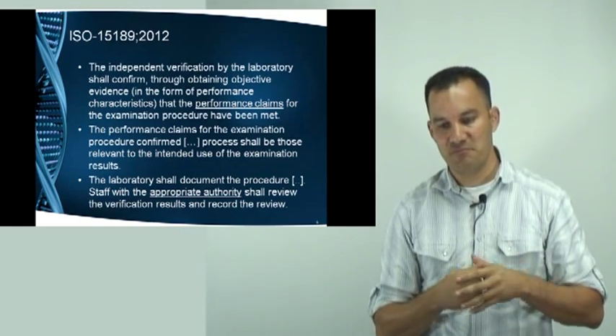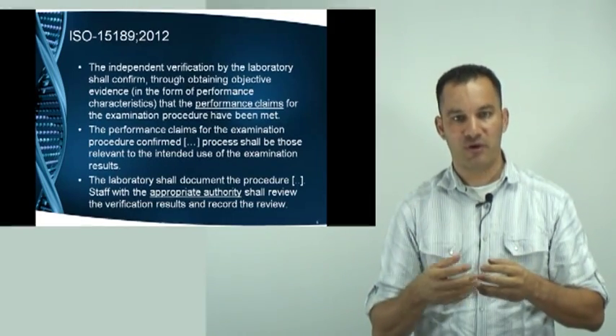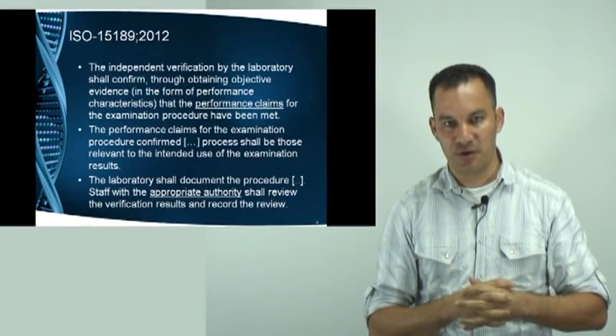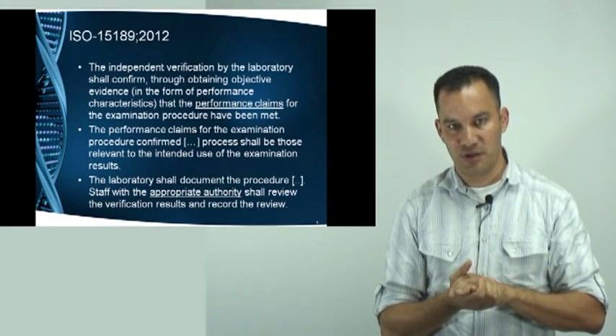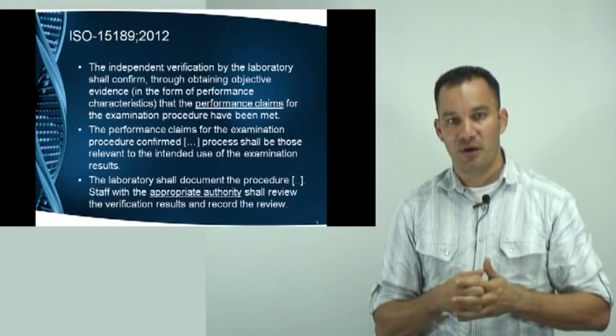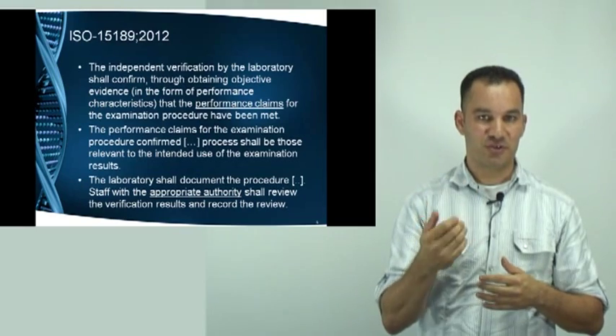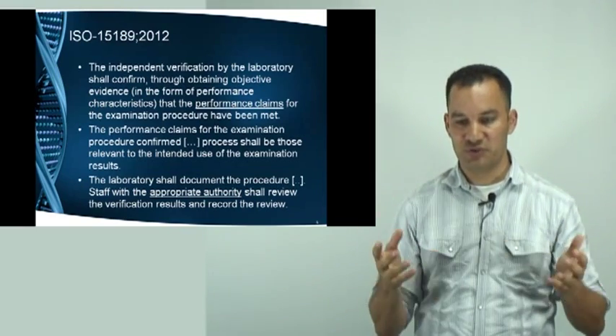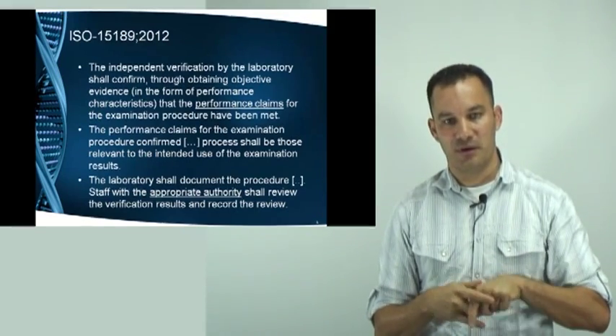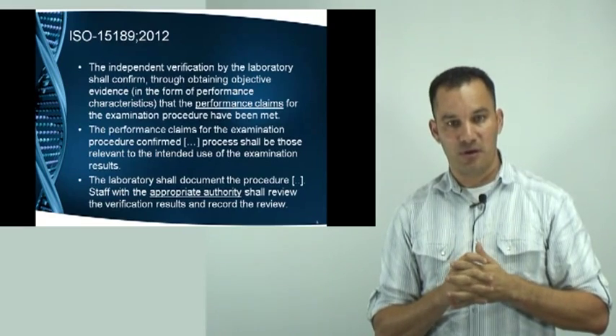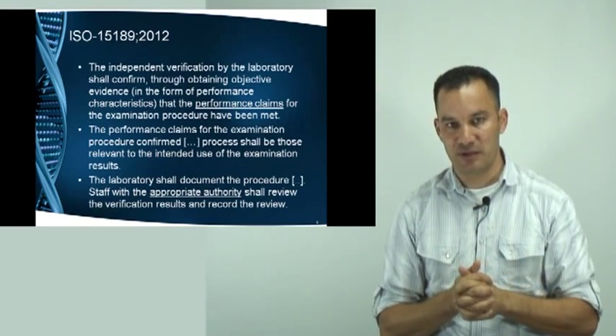Another part of ISO 15189 states that we should confirm using objective evidence — we have to perform experiments to demonstrate that the performance claims made by the manufacturer, such as a precision of 3%, are something we can also achieve in our own laboratory. Those experiments should relate to the intended use of the test.